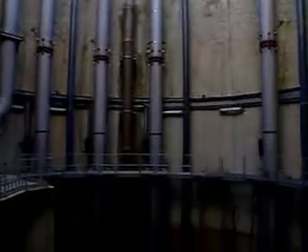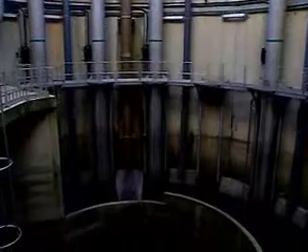A proper design of the pump sump for sewerage and stormwater systems is crucial. Two important design requirements to be met are preventing significant quantities of air from reaching the impeller and disposal of settled and floating solids. Operating costs can be reduced with the help of effective planning and suitable operation schedules to achieve optimum pumping performance and maximum pump life. Pumps are used for many different purposes: drainage, circulation, distribution and pressure boosting systems, each having different installation methods. For wastewater, pumps are installed in a sump.